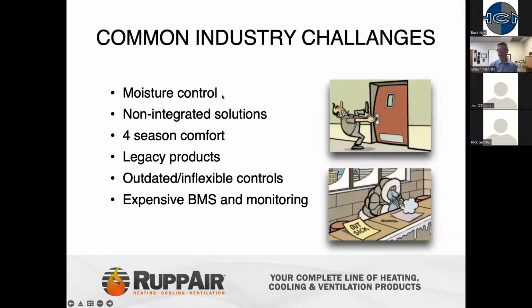So as we talked about, common industrial challenges. Within the warehouse industry, the biggest thing you're going to see, especially in these speculative tilt buildings, is moisture control, moisture issues that may exist in the building. Non-integrated solutions: we have multiple manufacturers providing different products to the warehouse that may not interface with each other. One exhaust fan may not talk to a heater, may not talk to a damper that's opening and closing elsewhere in the building. So having that integration.